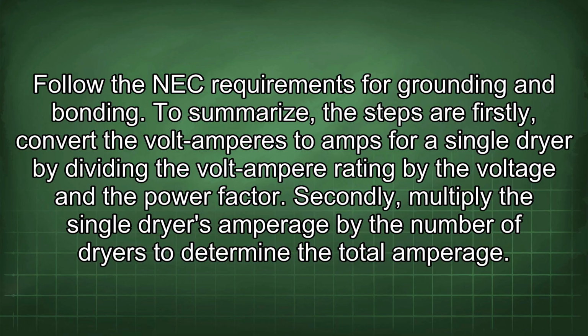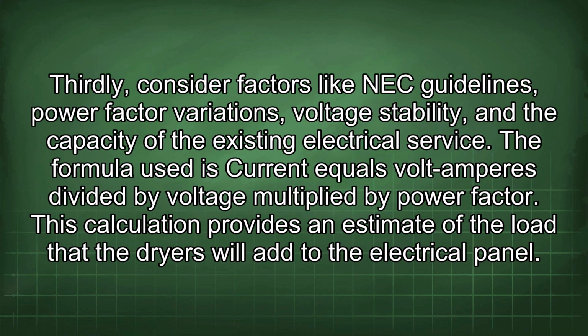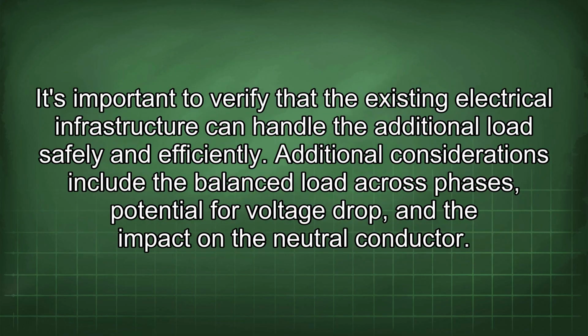Secondly, multiply the single dryer's amperage by the number of dryers to determine the total amperage. Thirdly, consider factors like NEC guidelines, power factor variations, voltage stability, and the capacity of the existing electrical service. The formula used is current equals volt-amperes divided by voltage multiplied by power factor. This calculation provides an estimate of the load that the dryers will add to the electrical panel. It's important to verify that the existing electrical infrastructure can handle the additional load safely and efficiently. Additional considerations include the balanced load across phases, potential for voltage drop, and the impact on the neutral conductor.